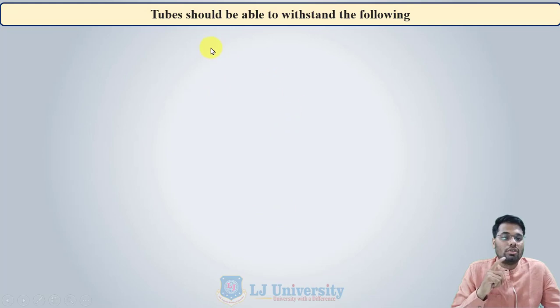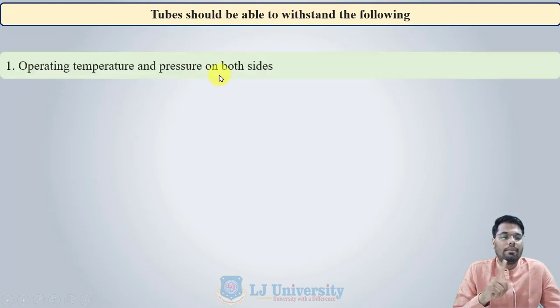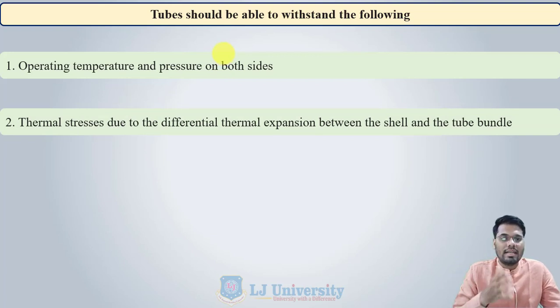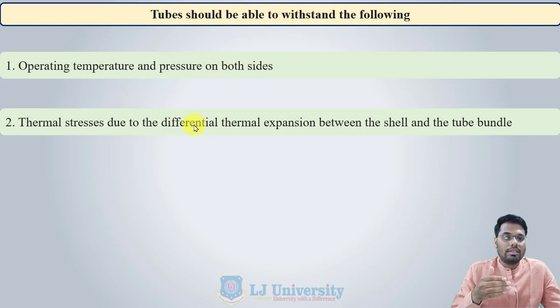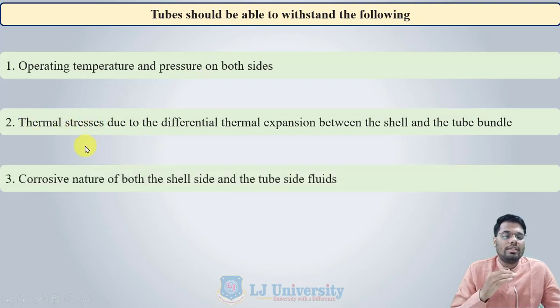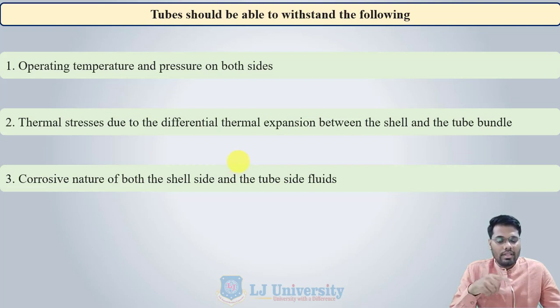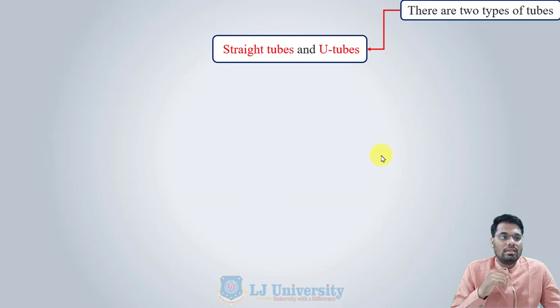The tube must be able to withstand: first, operating temperature and pressure on both sides — inside and outside — since shell side fluid flows over the outer surface and another fluid flows inside the tube; second, thermal stress due to differential thermal expansion between the shell and tube bundles from large temperature differences; and third, the corrosive nature of both shell side and tube side fluids, since one fluid contacts the outer surface and the other contacts the inner surface.